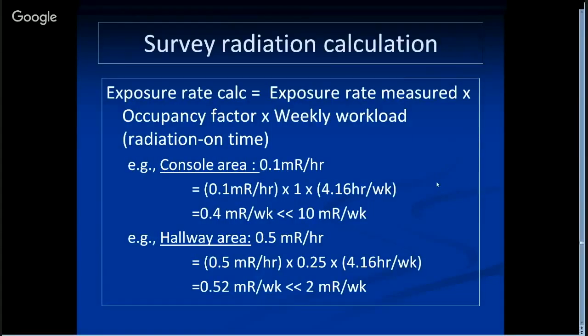Here's an example, we already surveyed and got the exposure rate. For the console area, we got 0.1 mR per hour, and you can calculate that. So you have measured data, occupancy factor, beam on time, and finally you get that data, which is far below the 10 mR per week limit. We also did a hallway survey, and that data showed 0.5 mR per hour, which when calculated is much less than the limit.